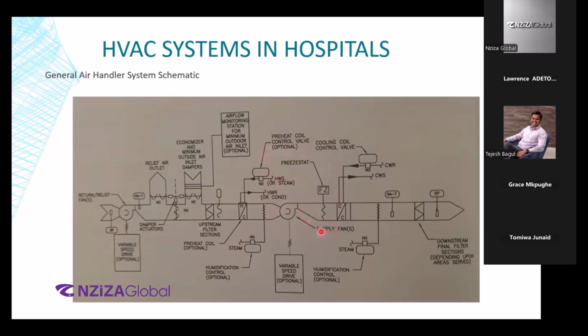In our countries, it doesn't get that cold, so there are not many chances of elements to freeze. But let's say Canada, North of America, Russia, these countries get to very sub-zero temperatures. At that time, the freeze stat is used to ensure that proper monitoring is done for the airstream and nothing might lead to any freezing of the components. That is what it is used for.